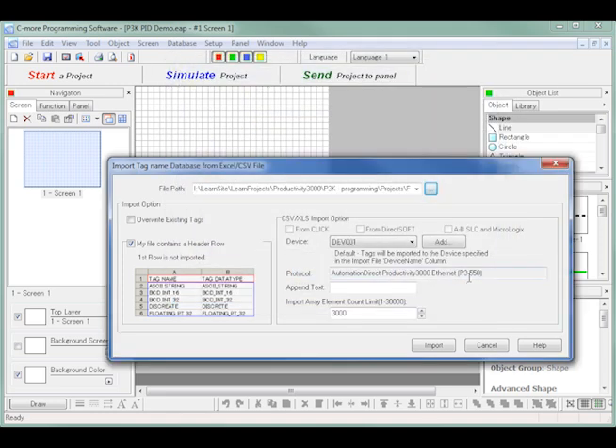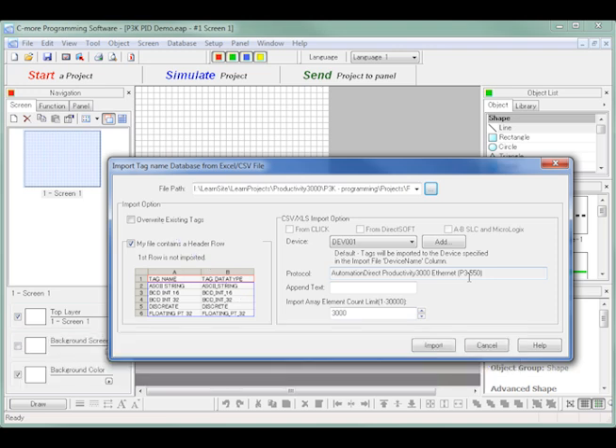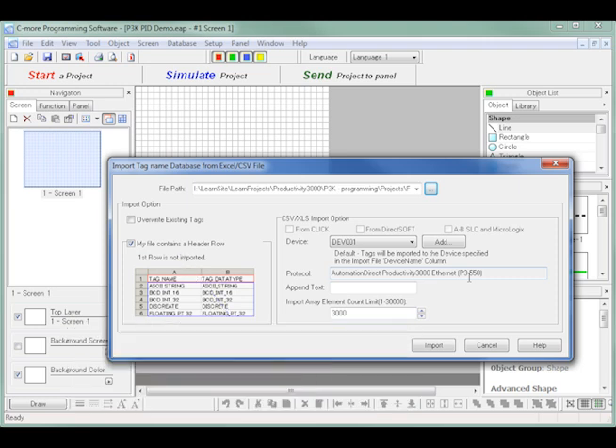You will notice I have not checked Overwrite Existing Tags since this is the first time I am importing to my C-more project. But I do have my File Contains a Header Row checked because the exported CSV file from the Productivity 3000 project does have header rows. For my needs, I have kept the defaults for the CSV/XLS import option.